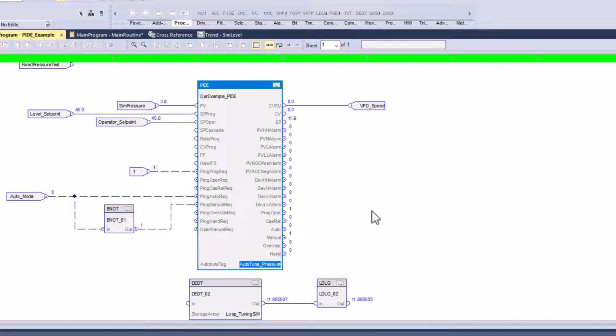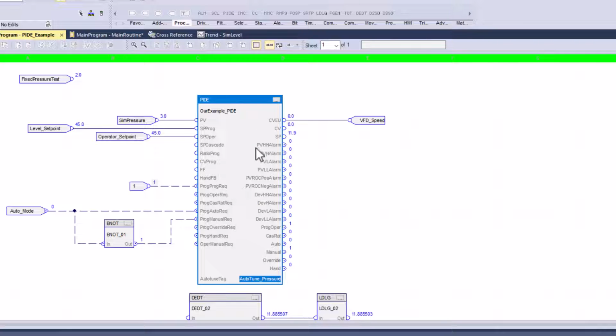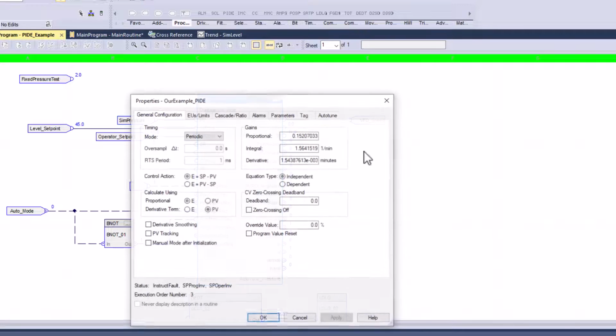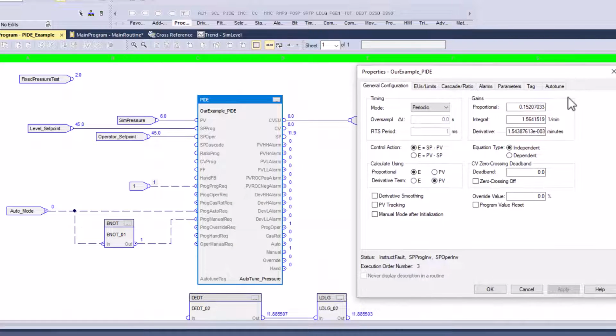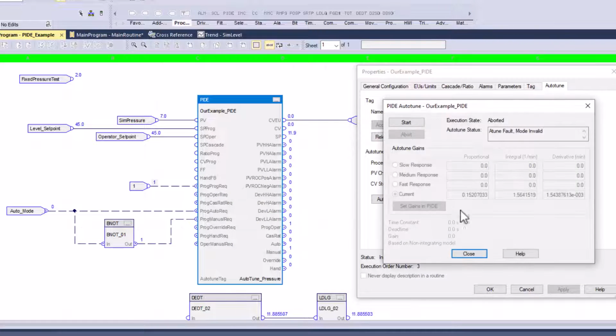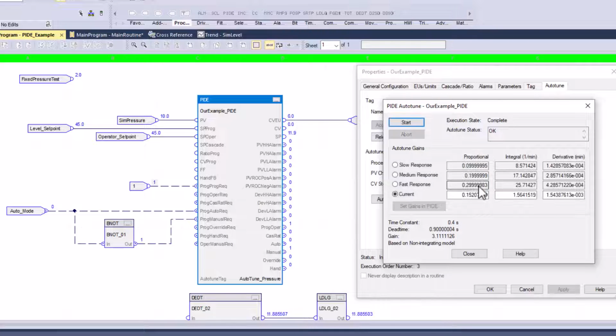What we want to do now is continue our talk on the actual PID tuning. So let's just go in here and see. Right now our PV is changing. Okay, so let's see if we can tune it the way it is. All right, let's try to tune again. It says in process, and you can easily see that it's trying to do something, and it actually comes up with a tuning. So sometimes if your loop is changing too rapidly, it won't have this effect. So this is pretty strong.